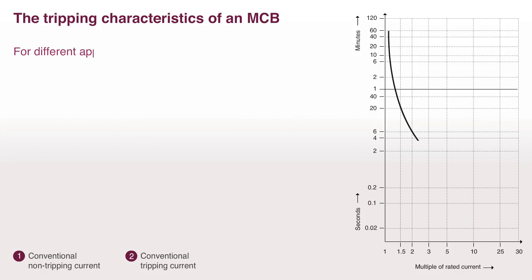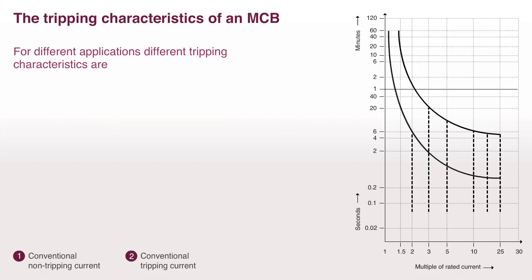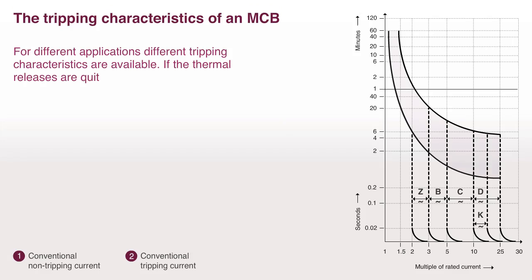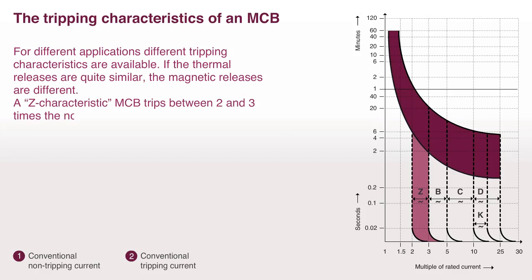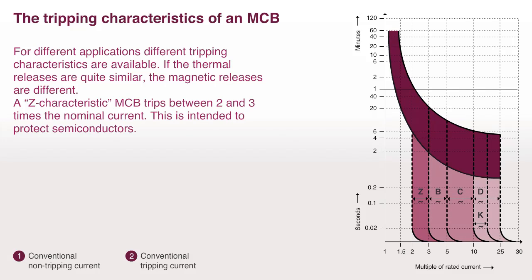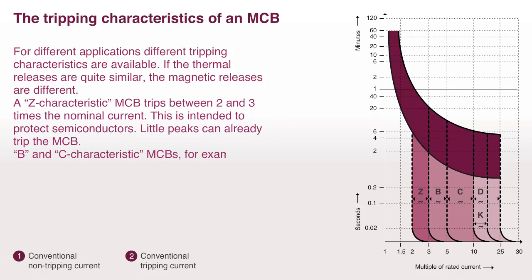For different applications, different tripping characteristics are available. If the thermal releases are quite similar, the magnetic releases are different. A Z characteristic MCB trips between 2 and 3 times the nominal current — this is intended to protect semiconductors. Little peaks can already trip the MCB. B and C characteristic MCBs are used to protect cables.